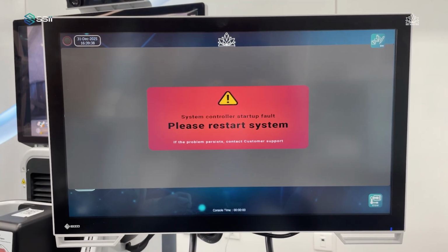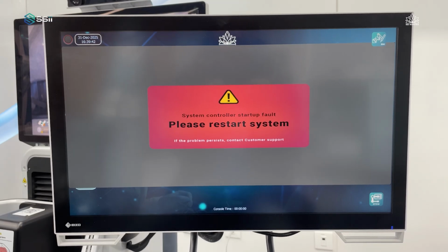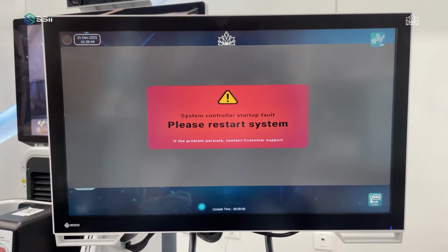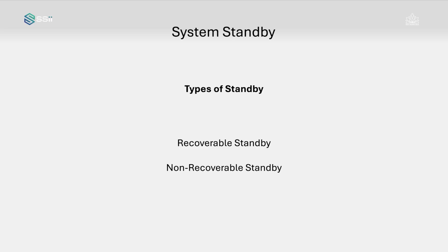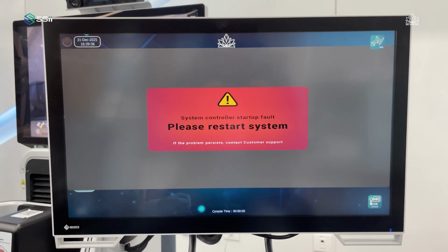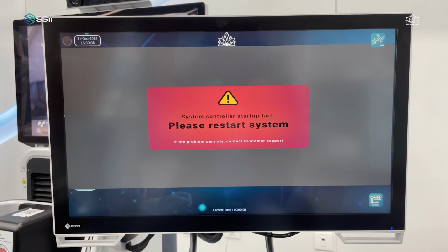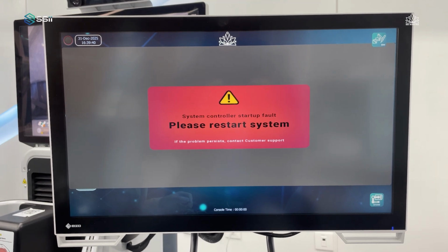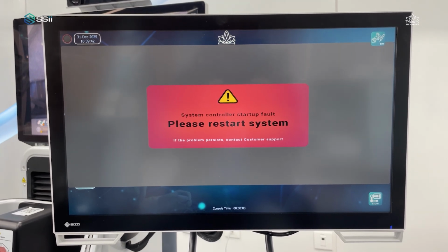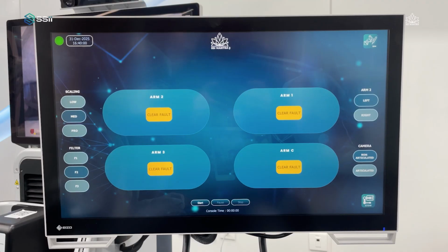When standby is encountered, users are advised to wait for up to 2 minutes, as the system may attempt automatic recovery. System standby is further classified into recoverable and non-recoverable standby. In recoverable standby, system communication is restored automatically and the "Please restart system" message disappears, followed by the normal operating screen on the SSI viewer with a clear fault button displayed on all arm controls.